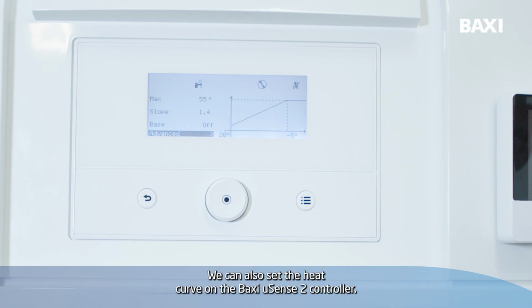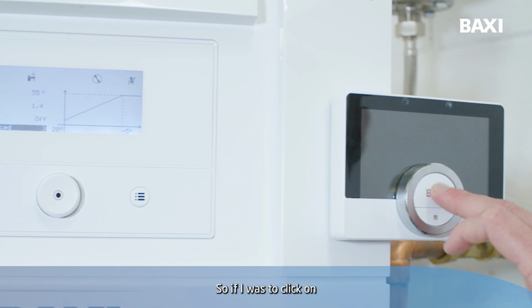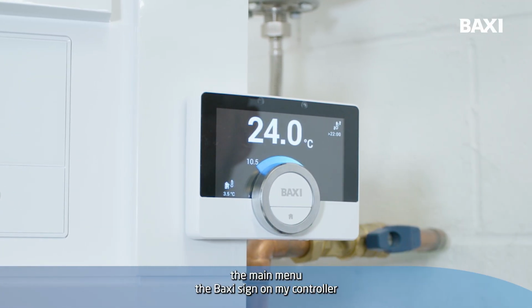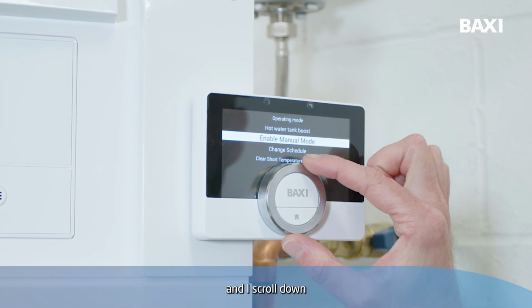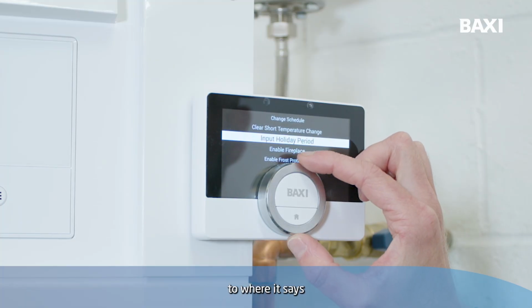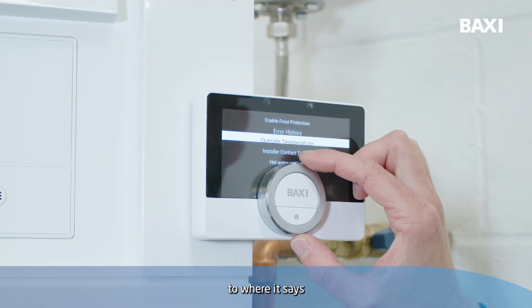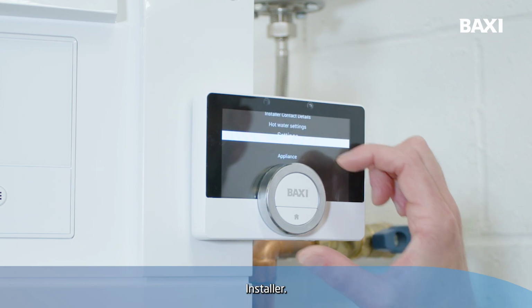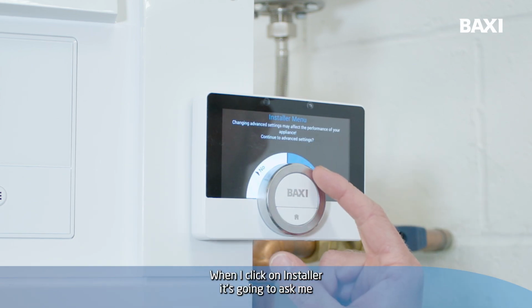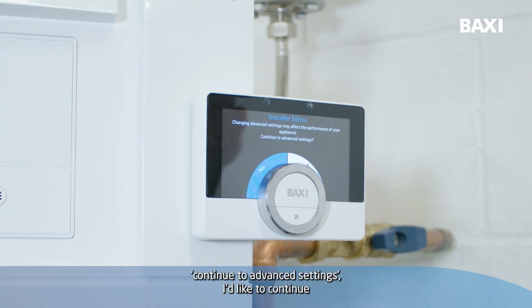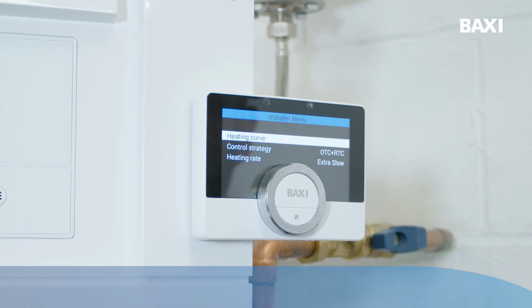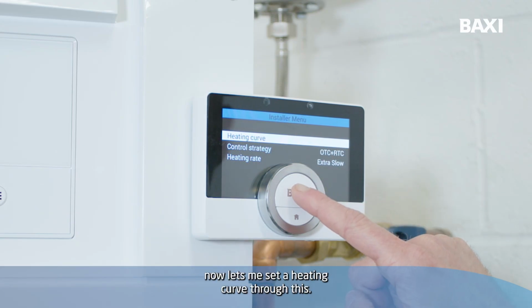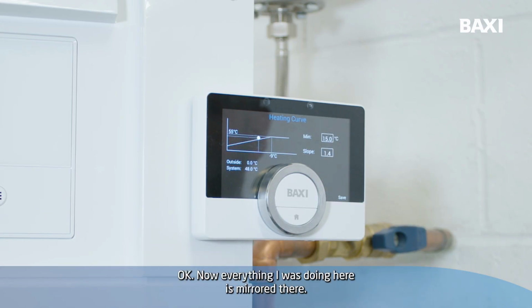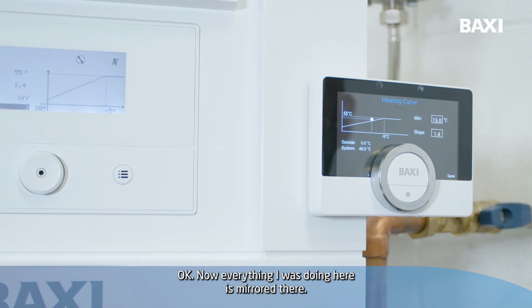We can also set the heat curve on the Baxi uSense 2 controller. So if I was to click on the main menu, the Baxi sign on my controller, and I scroll down to where it says installer, when I click on installer, it's going to ask me continue to advanced settings. I'd like to continue. And it now lets me set a heating curve through this. Okay, now everything I was doing here is mirrored there, all right?